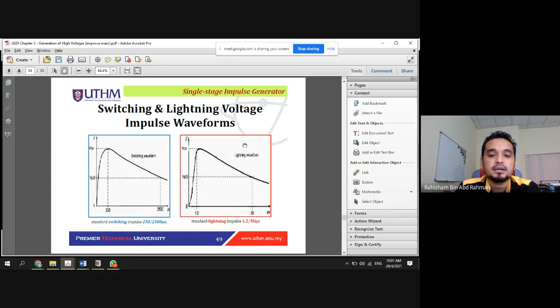We would expect all of you to be able to sketch this simple lightning or switching waveform. The shape can be slightly different and it's still acceptable. What's most important is the parameter, and it's a bonus if you can draw it exactly. In general they're identical except for the values of the rising and decaying time to 50% of the magnitude - for example, a waveform having a peak value of 150. So we have to decide, we have to be able to draw it.